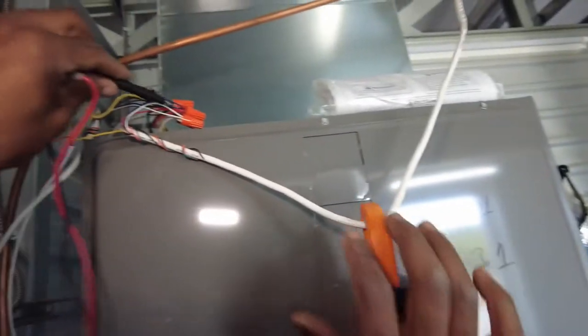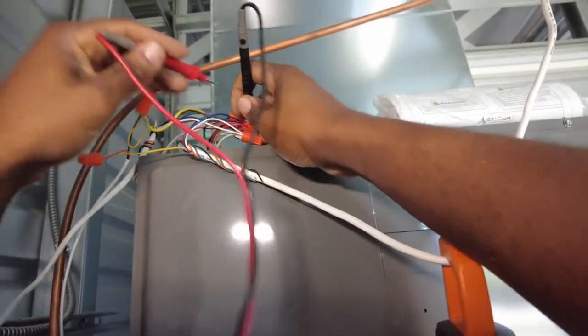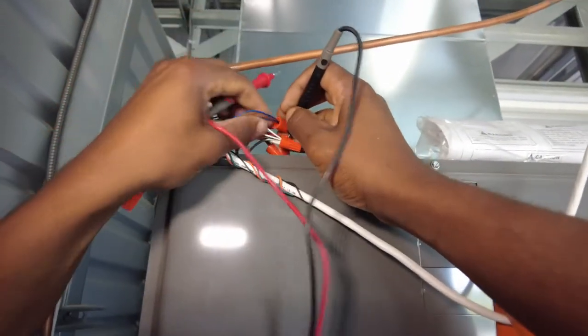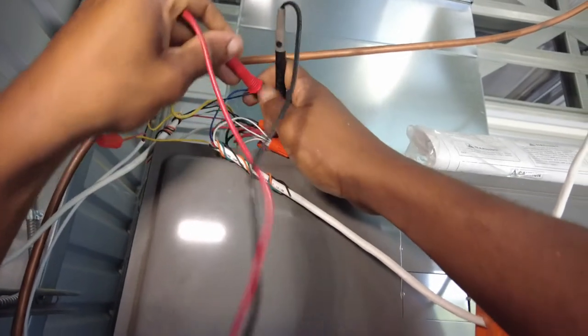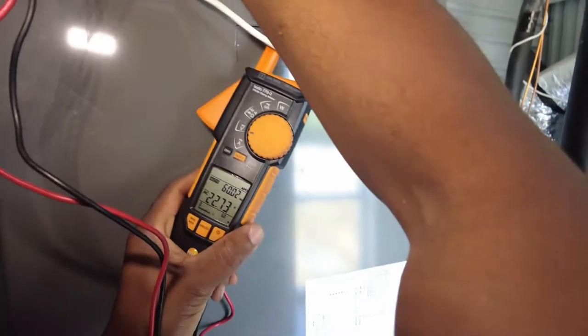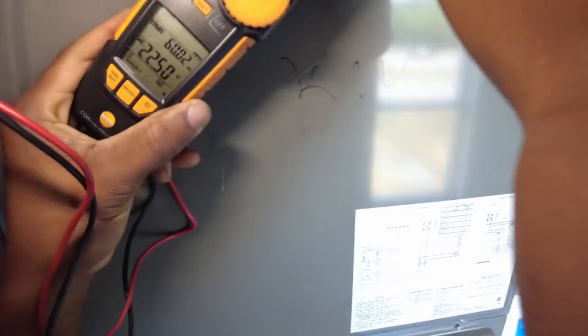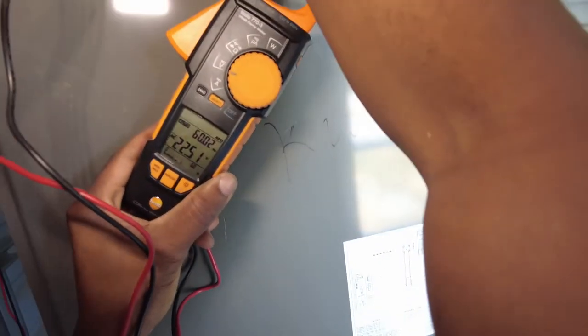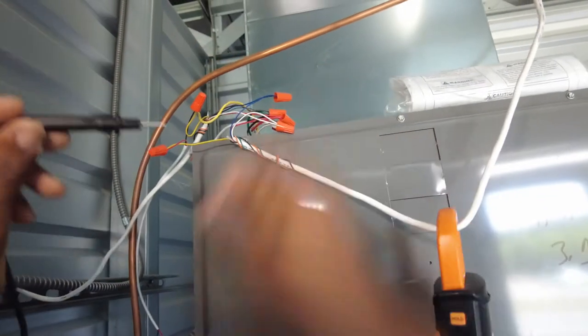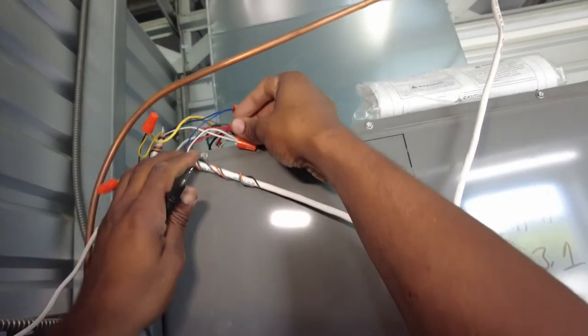Across my 24 volts and common. You see I'm only reading 22 volts, which is very low.